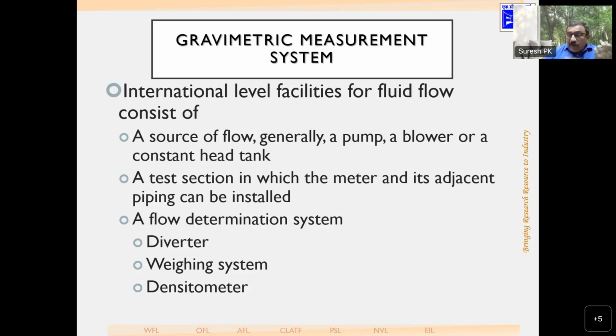So the level of water supplying to the flow meter is maintained. Therefore, the upstream head of the water is maintained at a constant level. That is why it is called constant head tank. So we will avoid any uncertainties due to the fluctuation in flow if you employ the constant head tank method.